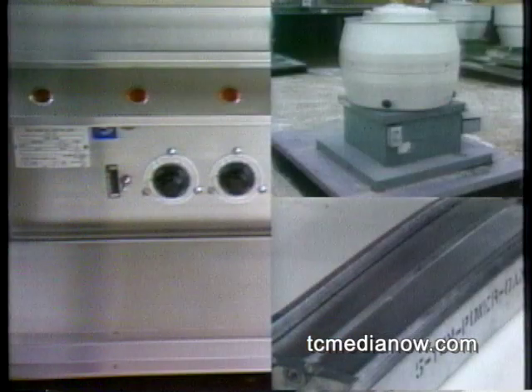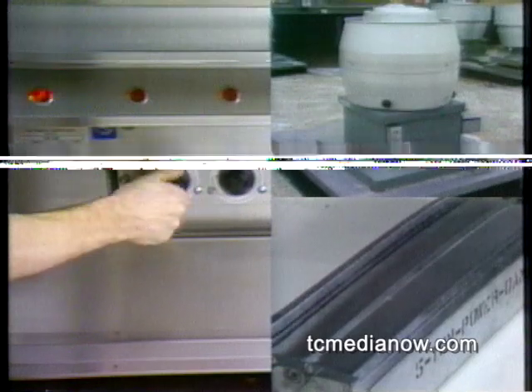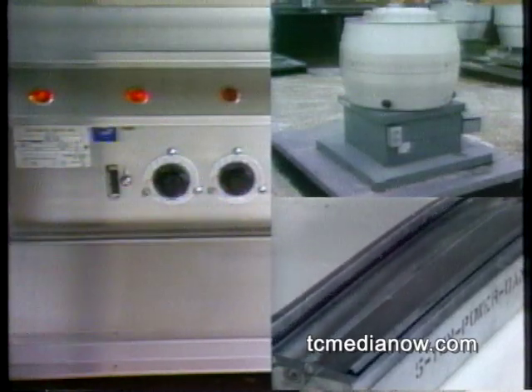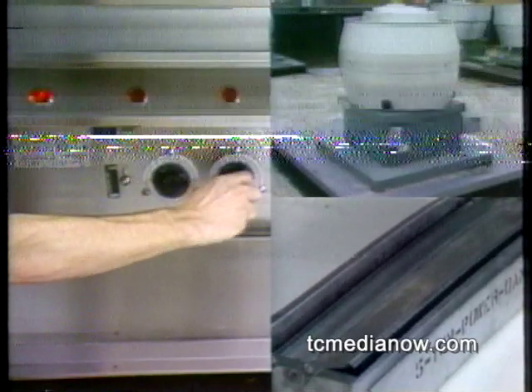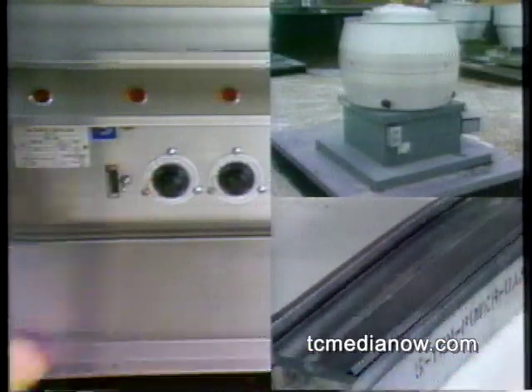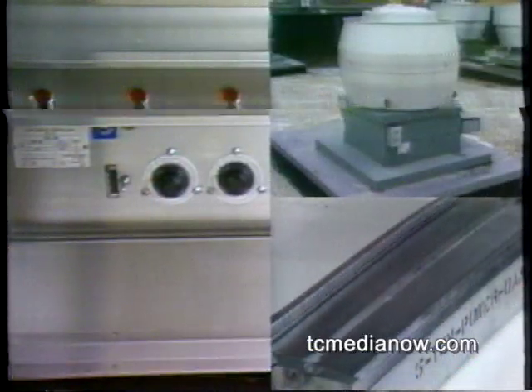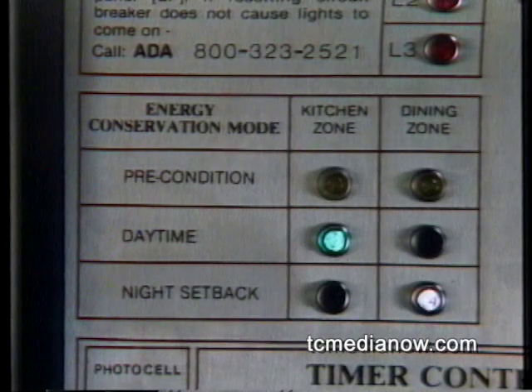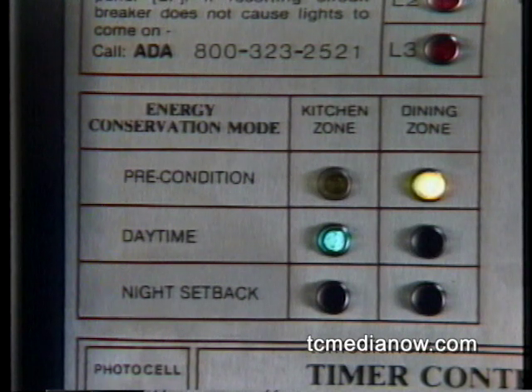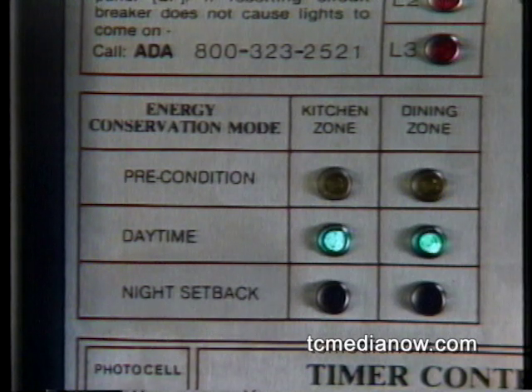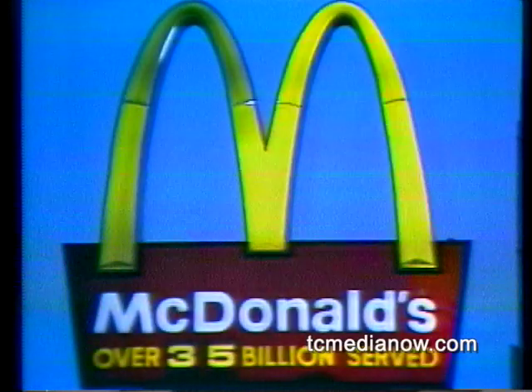When you do turn cooking equipment on or off in the system's daytime mode, the interlocked exhaust fan will automatically be turned on or off, and an outside air damper will open or close. A half hour before opening time, the dining room goes into precondition mode. Then, at opening time, the dining room goes into daytime mode, and the balance of the parking and soffit lights, the beam lights, and the road signs all come on, indicating the store is open for business.